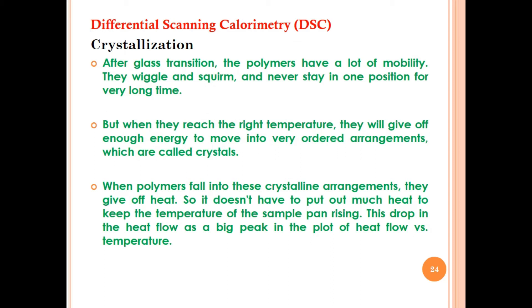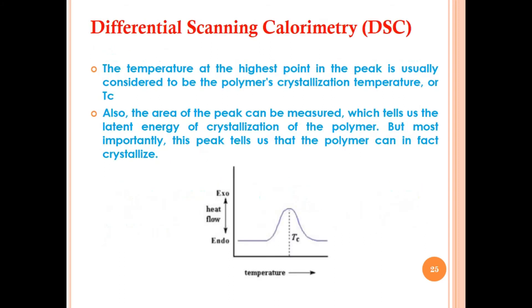From DSC, we can measure the phenomenon of crystallization after the glass transition. The polymer has a lot of molecular mobility — the chains wiggle and squirm. When they reach the right temperature, they give off energy to move into ordered arrangements called crystal arrangements. In the amorphous state there is no ordered arrangement, while in crystals there is an ordered arrangement of all atoms. When the polymer falls into crystalline arrangements, it gives off heat, so less heat is needed to keep the sample pan temperature rising. This drop in heat flow appears as a peak in the plot of heat flow versus temperature, and the temperature at the highest point of the peak is the polymer crystallization temperature, Tc.